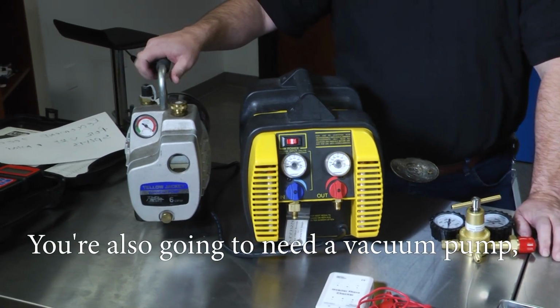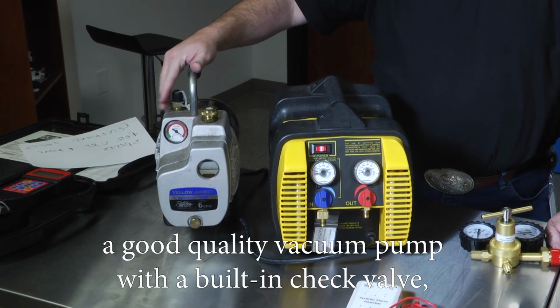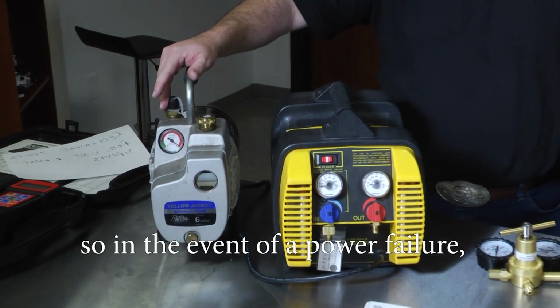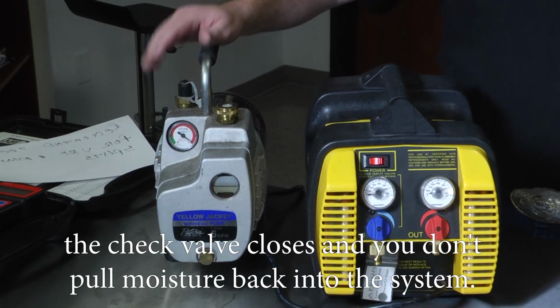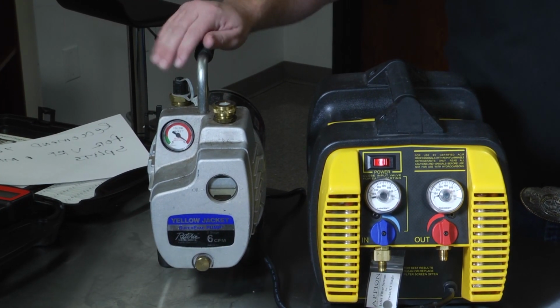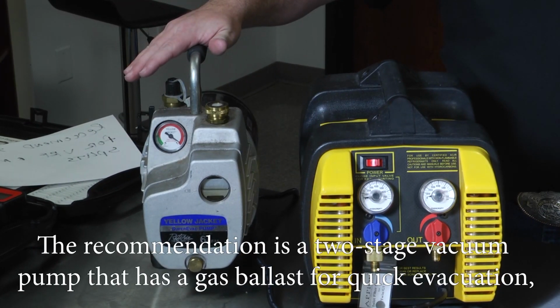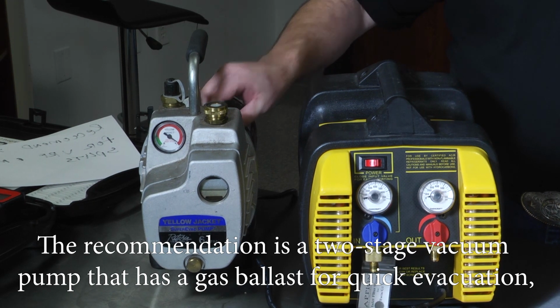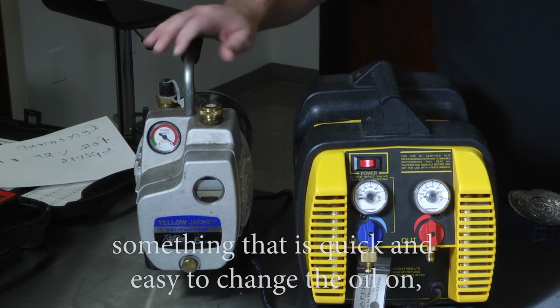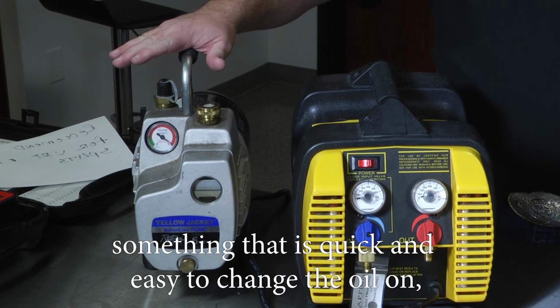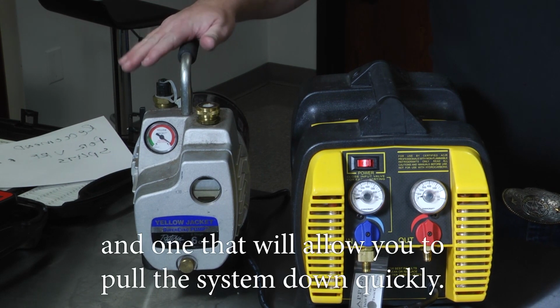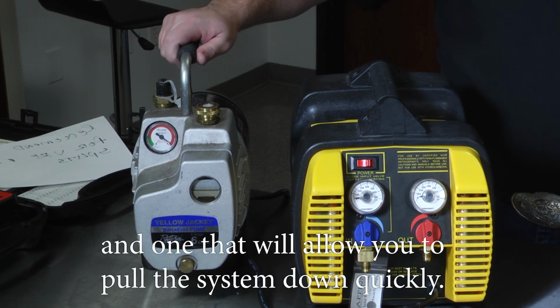You're also going to need a vacuum pump, a good quality vacuum pump with a built-in check valve, so that in the event of a power failure, the check valve closes and you don't suck moisture back into the system. The recommendation is a two-stage vacuum pump that has a gas ballast for quick evacuation, something that is quick and easy to change the oil on, and one that will allow you to pull the system down quickly.